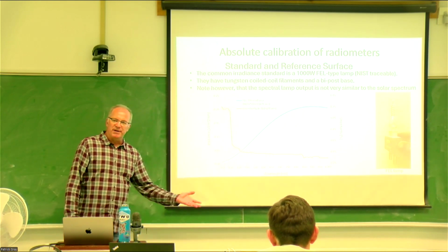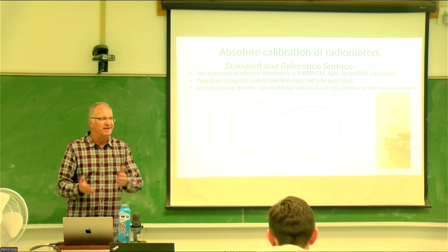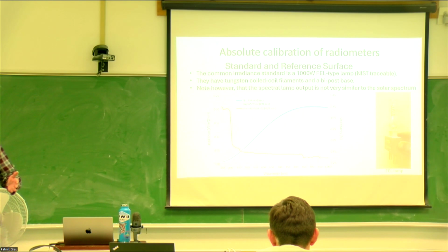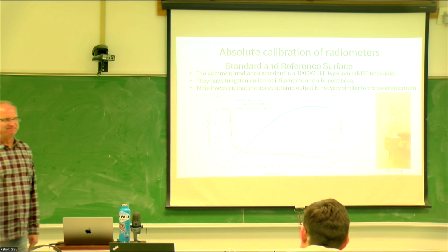So you have a 30-minute warm up, setup time, and calibration only takes 15 minutes. And then you have to burn it down slowly, ramp down the amperage to bring it back to a stable state before you can actually turn it off. That takes another 30 to 40 minutes.